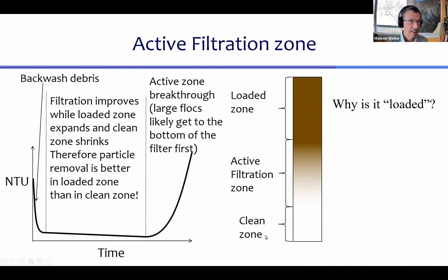Because think about it, at the beginning of a filter run, most of the filter is clean and a little bit of it is dirty. And that doesn't perform as well as a filter that is mostly dirty and has a little bit clean at the bottom. That means that the dirty part of the filter is actually doing a better job of filtration than the clean part of the filter. So that's comparing the loaded zone and the clean zone.